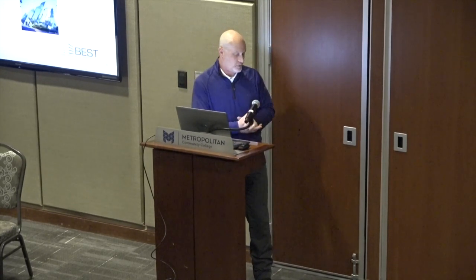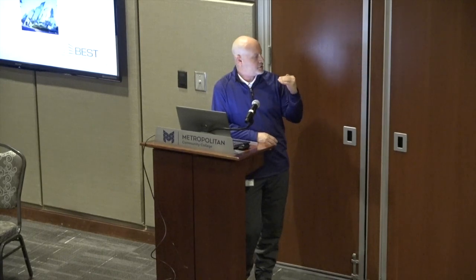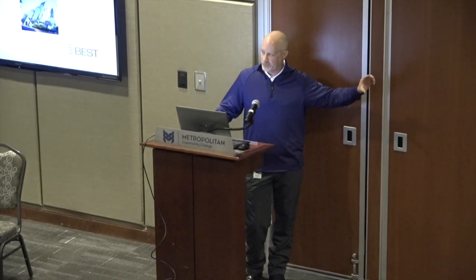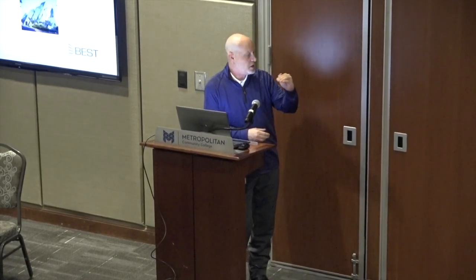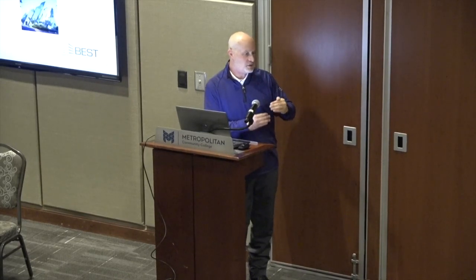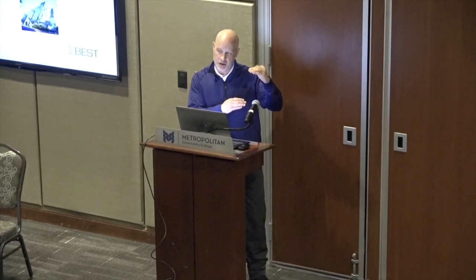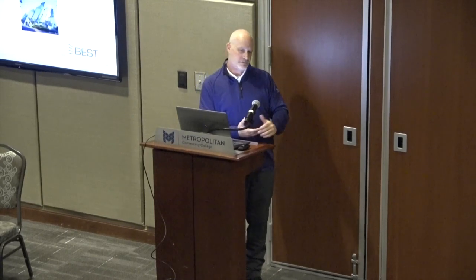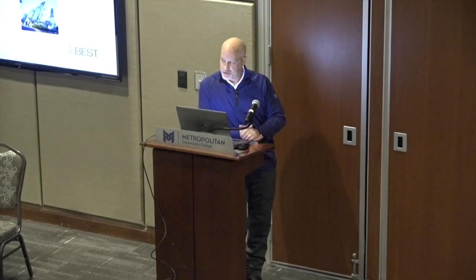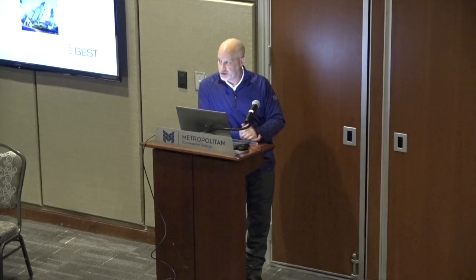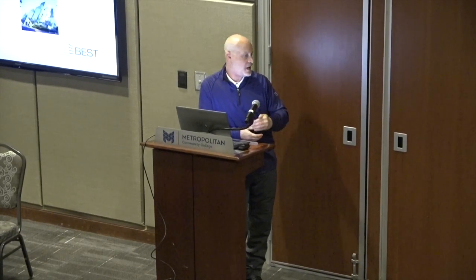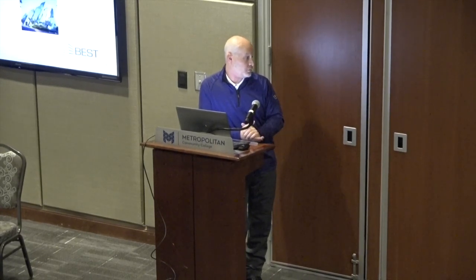Comfort, let's just pick comfort. And we know that we have a set point. How far above that set point did it deviate? How far below it did it deviate? And how far did it happen every day for the last year or so? It gives us an opportunity to see that trend over the history. Okay, now this piece of equipment started to deviate a little bit more every day. But we figured that a building drifts considerably, 10 to 15% a year. So if we see that coming, that's one algorithm that we can look at.